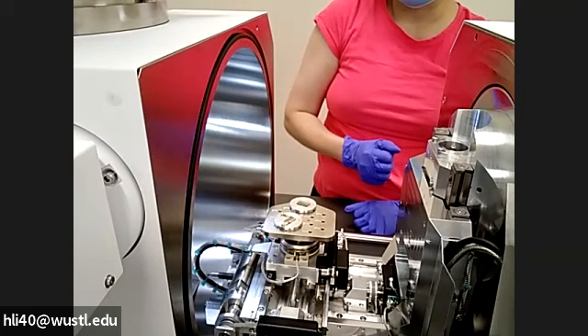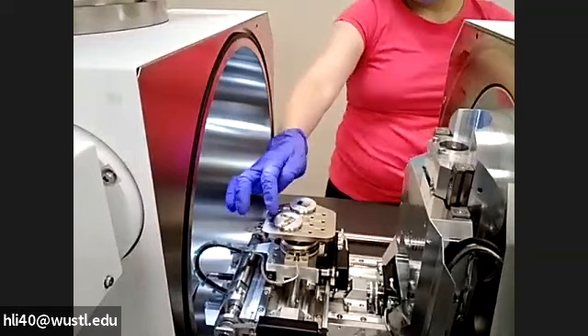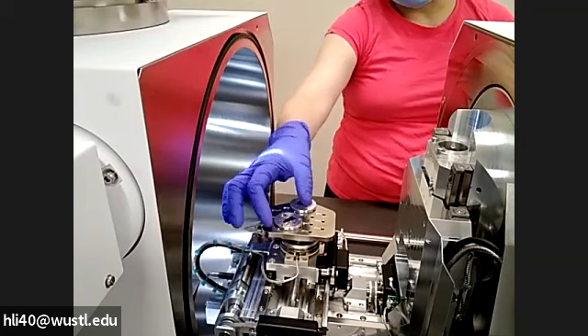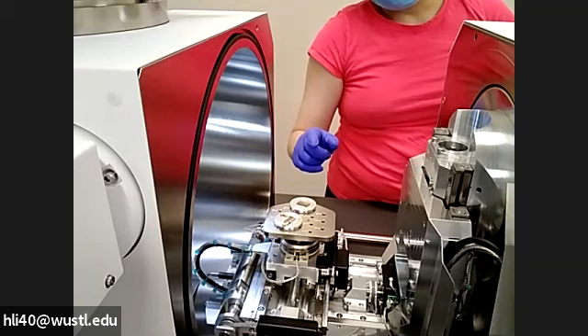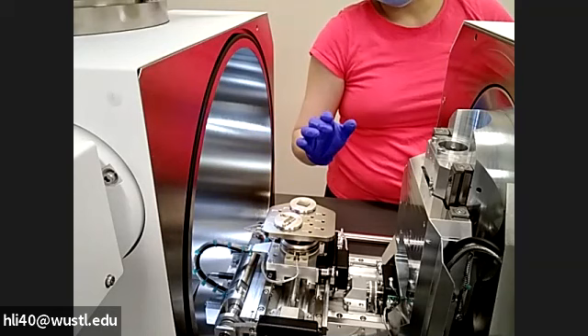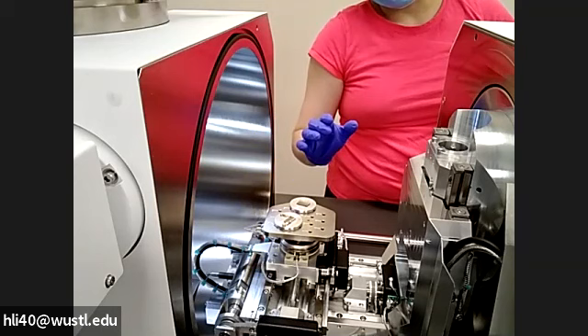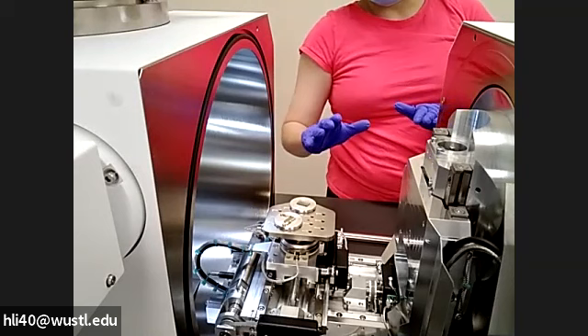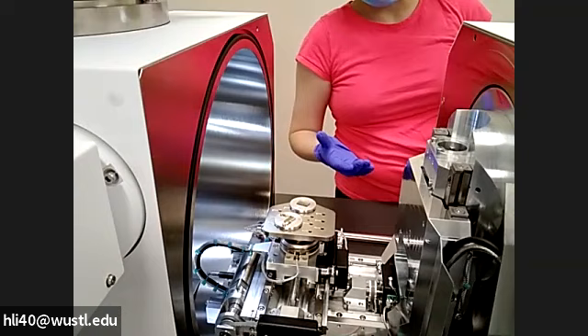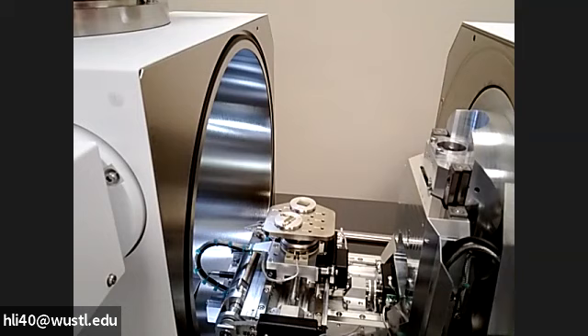So after you mount the sample, make sure your sample has similar height, okay? You push all the way in. When mounting, you have to make sure the sample has similar height. I emphasize this here, it will be much more convenient for you to operate, especially if your sample happens to have a different height than what you mounted. So just mount the similar height ones and move to the next step next time. The sample exchange won't take long, so it will be okay.